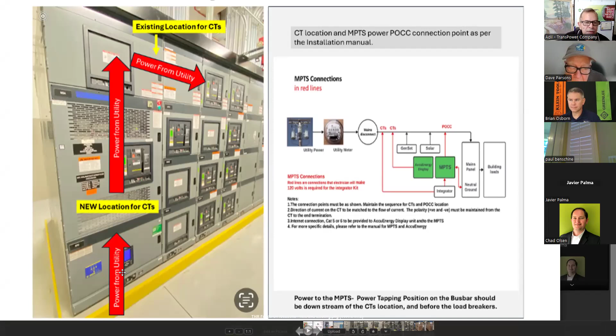So now when you look at this as a switchgear, when I said the power is coming in from the utility from the bottom here, okay? What they did was they installed the CTs somewhere here. Actually, it's not even in this panel. It is on this panel here, the second row of the panels. And then you have this bus bar running horizontally and vertically. Goes up, goes that way, comes down, goes up, comes down, goes up. So it's running all over. So what happened was these CTs ended up, the first time he installed it, here. Because see how easy it is? You open this panel and install it here. It is even past all the loads.